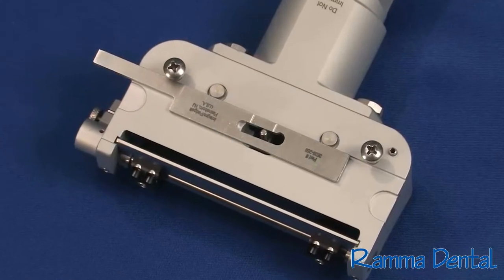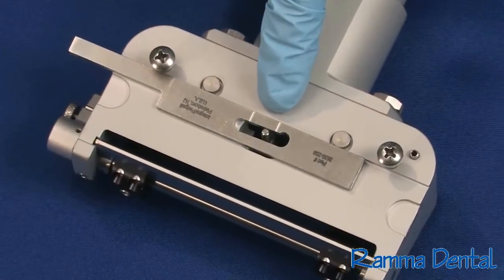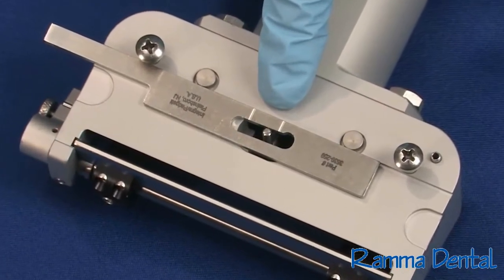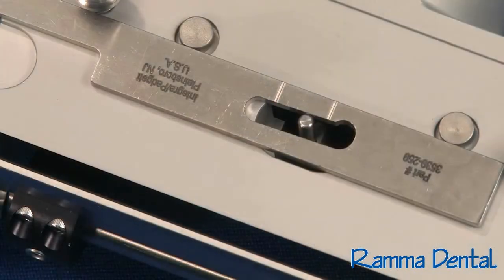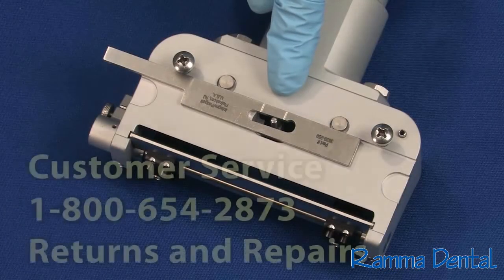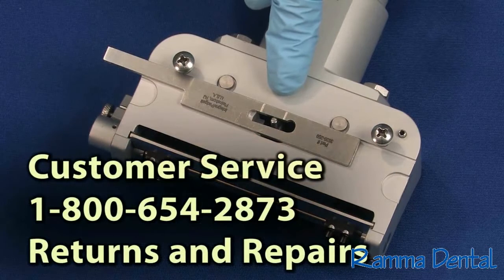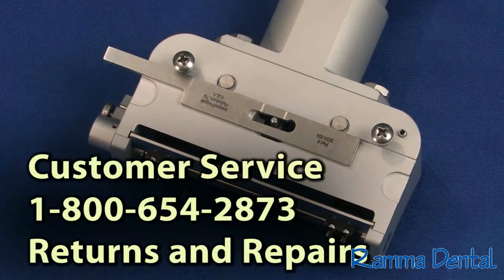If the pin is between the 2 hash marks on the gauge, the unit is functioning properly. Note that the oscillating pin moves from side to side during its normal operation, and a proper measurement should be taken without adjusting the position of the oscillating pin. If the pin is outside of its normal calibration, please contact your Integra customer service representative at 1-800-654-2873 and select the option for returns and repairs.